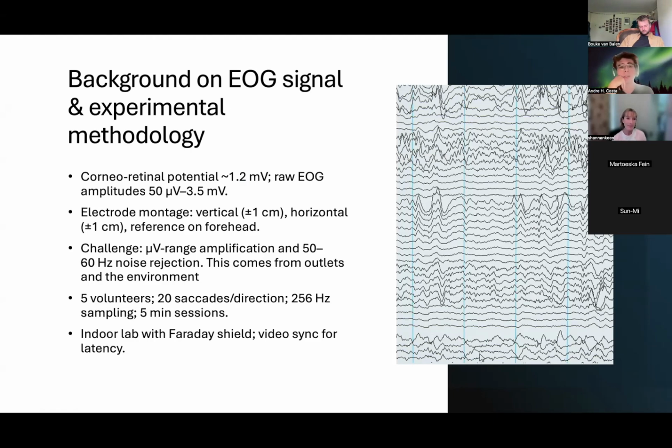So the main challenge was in the microvolt range, so very little actual measurement, which is what usually happened when we had our baseline, which we found in research to be at a max about 1.2 millivolts. If you move down, that amount would fall significantly. Once you're in that microvolt range, it's very difficult to measure anything. So that was our biggest challenge, but it's something I feel we addressed fairly well. And I'll show you some of the earlier outputs we had, just to show the difference in measurements there.